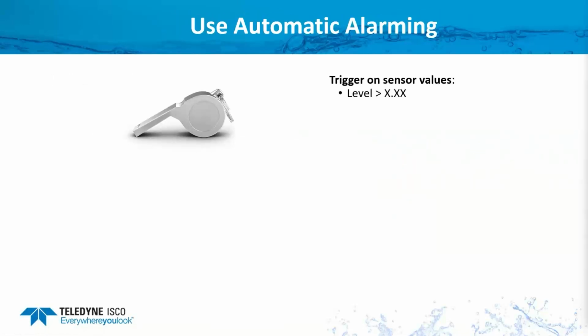So as far as the alarming, just some examples here. You can trigger on different values. So you could tell it when my level is greater than X. So remember, going back to that Flume, my level should always be, we'll say, around 4 inches or less. If I see it go up to 12 inches, well, then I know that's a problem. So you want to get alarmed right away.